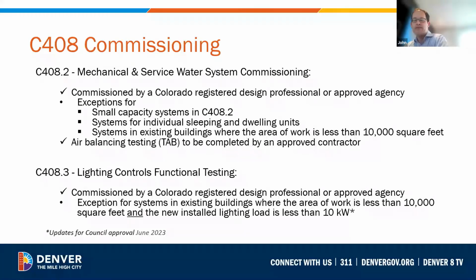Now, when is commissioning required? Per C408.2 of the Denver Energy Code, under Section 408, mechanical and service water heating systems must be commissioned when the total equipment capacity is 480,000 BTUs per hour, or 140 kilowatts, or in other words, 40 nominal tons or more of cooling capacity, or the combined service water heating and space heating capacity is 600,000 BTUs or more. Systems serving individual dwelling units and sleeping units are exempt from this requirement, and systems in existing buildings where the area of work is less than 10,000 square feet are also exempt.